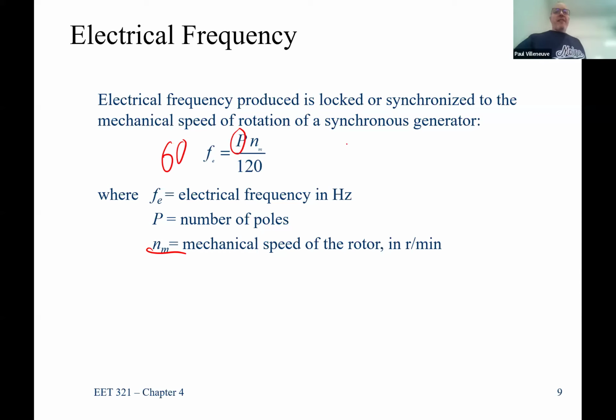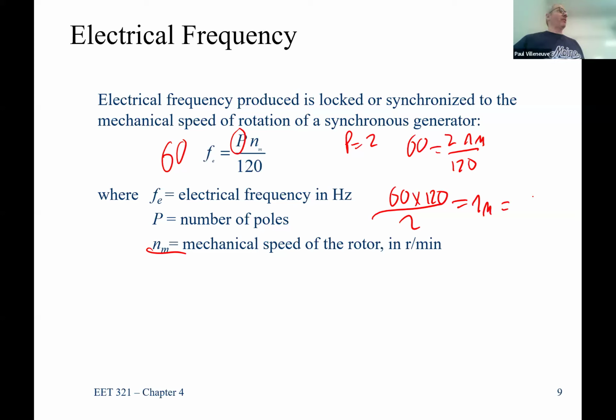Okay, so if you have P equals 2, we have n equals 120 f divided by P. So 60 times 120 divided by 2 equals n sub m, which is 7,200 over 2, 3,600. RPM is the unit. If you have 4 poles, then that becomes 1,800 RPM. And on and on, right?